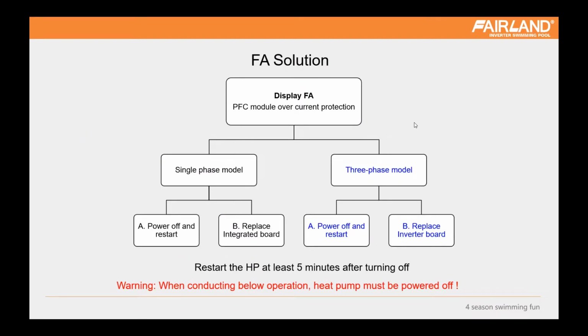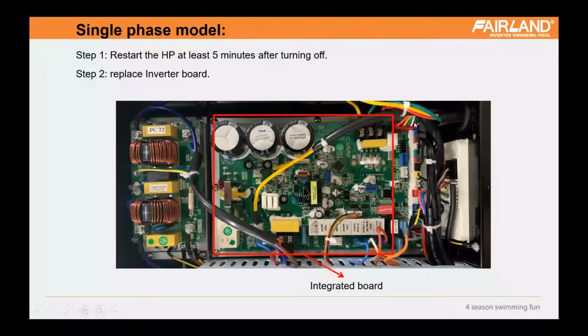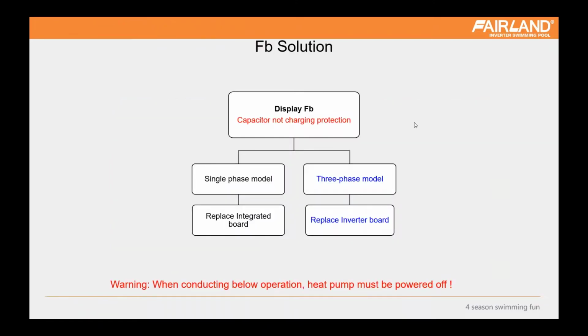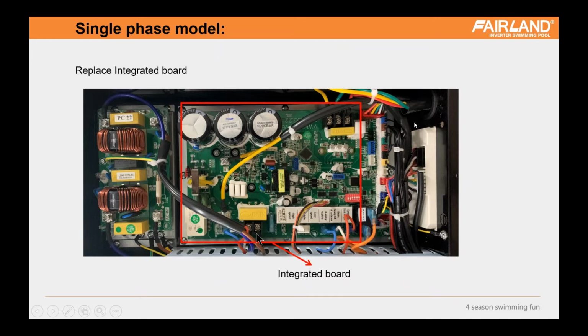FA is PFC module overcurrent protection. It's the same: replace the integrated board, and before that, reset the unit to try if it can recover or not. FB never happened. It is normally for three-phase models, but if it happens on a single-phase model, it's also about the integrated board, a program issue.